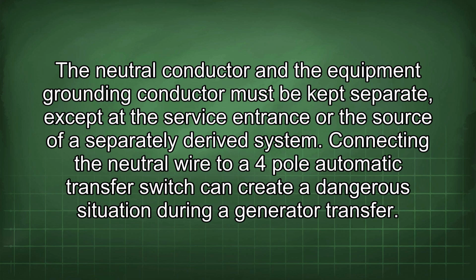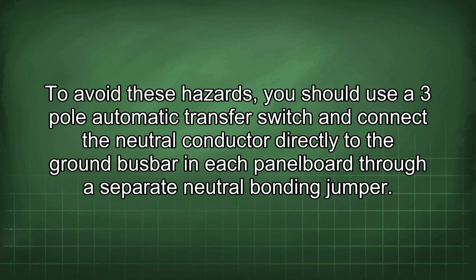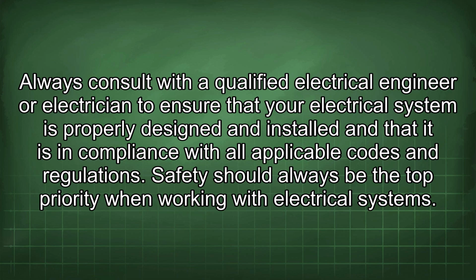Connecting the neutral wire to a 4-pole automatic transfer switch can create a dangerous situation during a generator transfer. To avoid these hazards, you should use a 3-pole automatic transfer switch and connect the neutral conductor directly to the ground busbar in each panel board through a separate neutral bonding jumper. Always consult with a qualified electrical engineer or electrician to ensure that your electrical system is properly designed and installed and that it is in compliance with all applicable codes and regulations. Safety should always be the top priority when working with electrical systems.